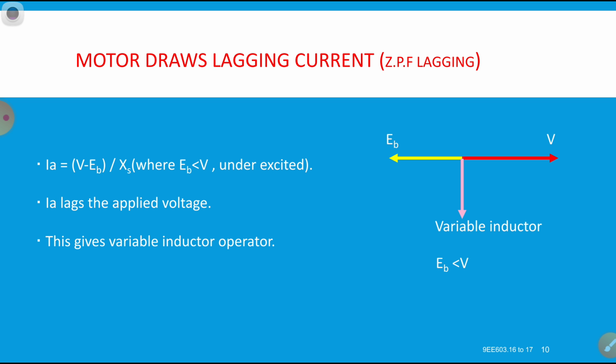If you connect this synchronous motor at the receiving end and operate it under under-excited condition, then instead of generating reactive power as previously, it now consumes reactive power, and it acts as an inductor. Under under-excited condition, the same synchronous motor draws current from the supply at a lagging power factor. Then the terminal voltage drastically changes to the normal value.